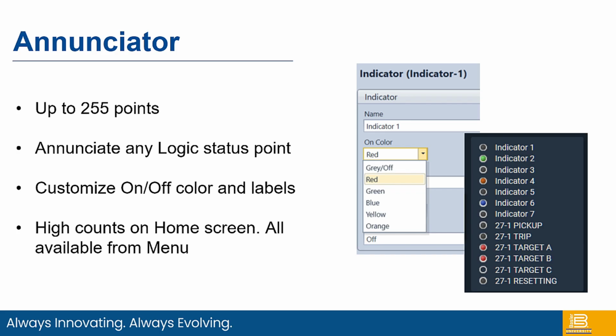These annunciators and indicators are programmed in logic, and you just drop them wherever you wish to in logic. In this particular example, I've got some single phase under voltage targets that somebody had wanted to annunciate, but literally any logic state if you want. Potentially you would want to know if your bus is healthy or anything like that, just tied to whatever logic chunk you wish, and then you have an annunciator.